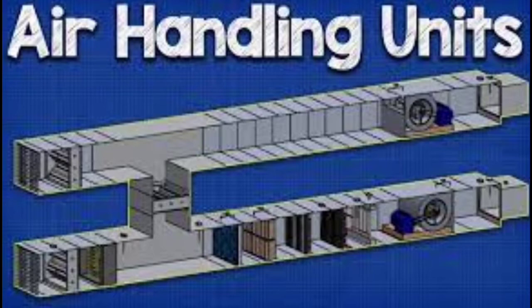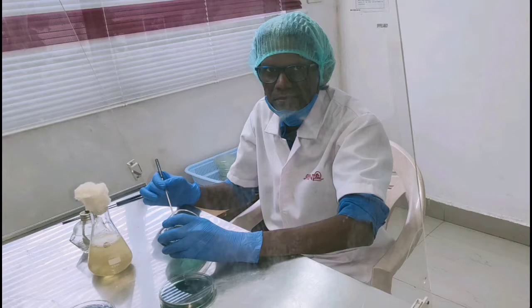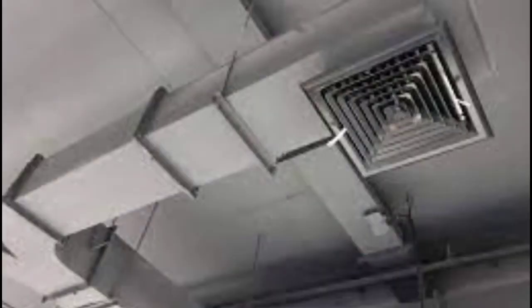Air filters should filter the contaminated particles in the air. The pure air should be supplied to the high risk area. As a QA team or QC team, we have to establish the air sampling frequency, depending upon the risk assessment. So we have to monitor the air load, the bacterial load in environmental samples, meaning air samples we have to collect from the positive airflow system. Always the air should flow from high risk to low risk area. So we have to equip an air handling unit for positive airflow.